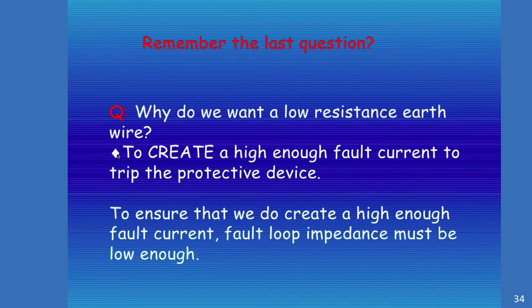Now we want to create a high enough fault level that the protective device operates. But we don't want to cause such a high level of fault that you actually damage the device. You can actually go too far the other way. So we want enough current that the device trips within a specified time, and that we don't actually create so much fault current that the device can't cope with it. So we need to ensure that we do create a high enough fault current or fault loop impedance must be of a low value.